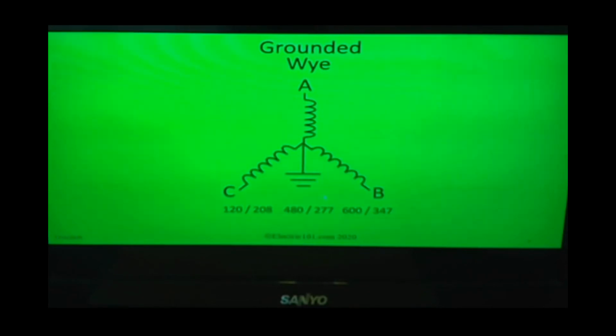But also in industry, you're going to have the same Y-type transformer that puts out 480, 277. So in other words, I measure between A phase and C phase, I get 480. I measure between A and B, 480. I measure between B and C, 480. So three-phase 480. But now we get the neutral here. I measure B phase to neutral, it's 277. I measure A phase to neutral, 277. C phase to neutral, 277. Probably the most common you see in large industries.